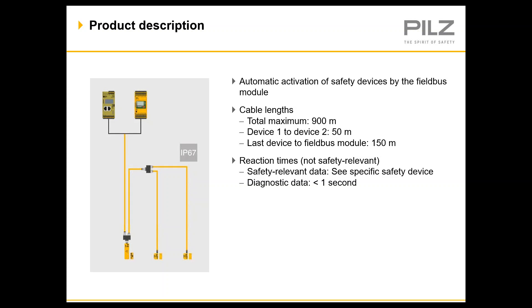Automatic activation of safety devices means that all you must do is plug the devices into a serial network. The SDD will find them and will immediately start collecting device information and status. Device status updates in under a second. Please note that this is not safety-relevant; safety update speeds are determined by the safety relay or controller selected.